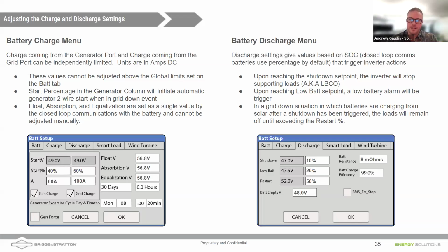The values can vary depending on how large the battery is. With a smaller battery, 10% might be a little low, but with a larger battery, you'd have more reserve to keep the inverter on in an idle state. So it depends. I'd say for a smaller battery, set the shutdown at maybe 15 or 20%, low battery 10% above that, and restart at 40% or higher.